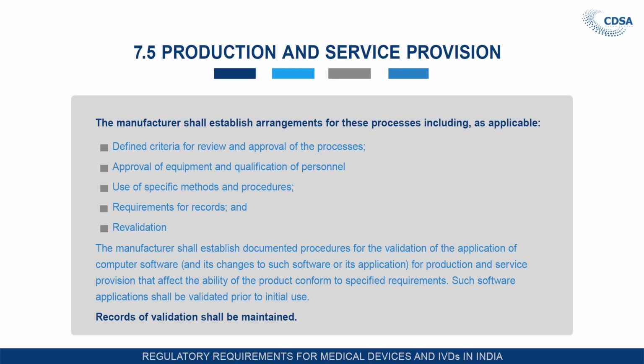So what is validation? If you read the first line very carefully, validation is for processes for production and service provision where the resulting output cannot be verified by subsequent monitoring and testing. That is, you cannot test and find out whether the process has gone through properly or not. In such cases, the processes have to be verified and validated repeatedly to show that the end result remains the same. In such cases, you don't require a final testing of the product, but if each process is validated properly by various means, your product at the end of the day will be the required product that you want to release to the market.